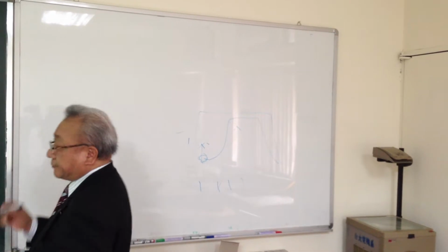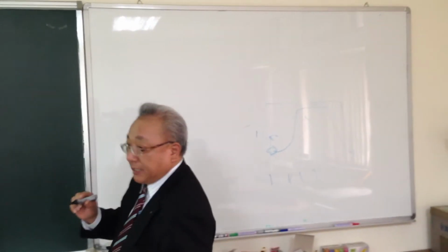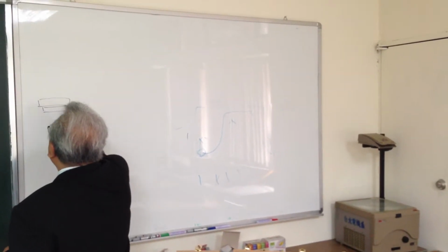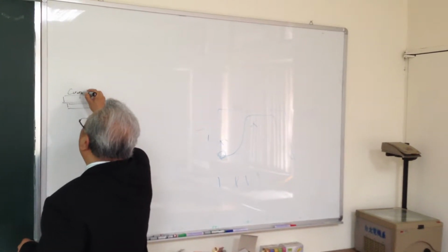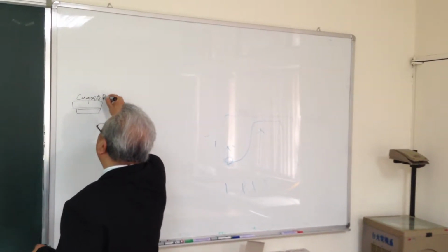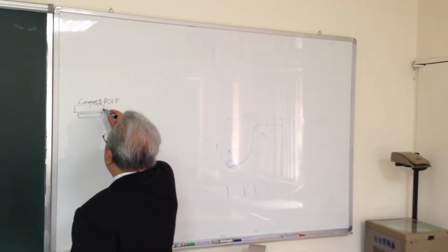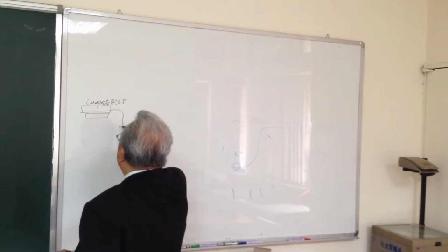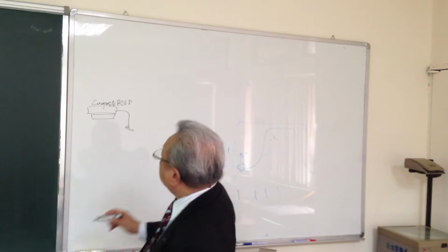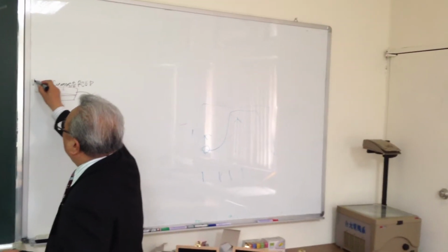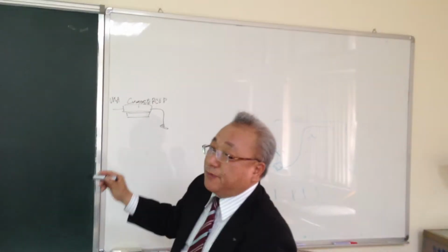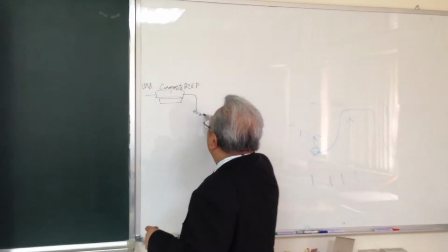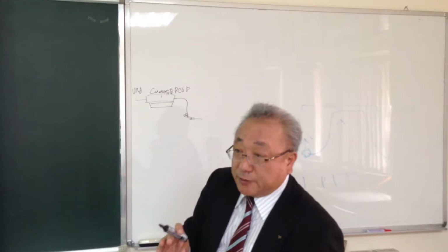For the receiver calibration, there is the composite receiver here, and maybe some cable to the probe tip. Then we calibrate the receiver, attached to the termination of the calibration substrate.